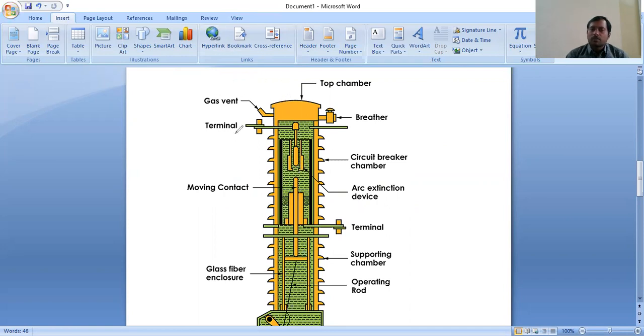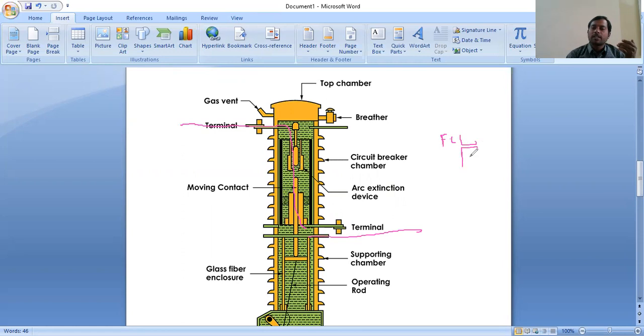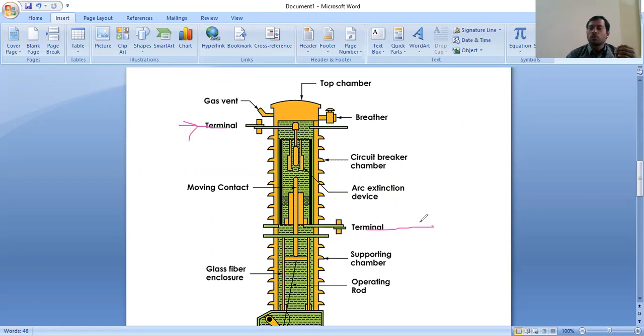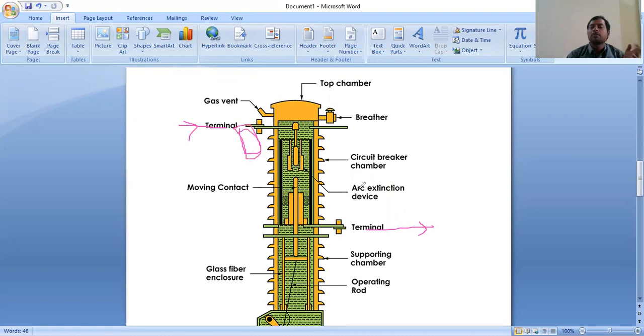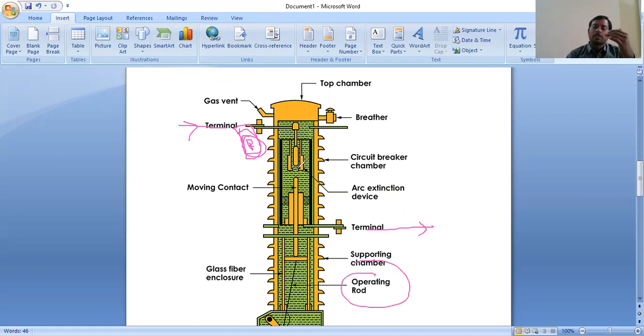In the normal condition, current flows from terminal one through the circuit breaker to terminal two. Both the fixed contact and the moving contact will be in contact mode — this is the normal condition. In the abnormal condition, whenever excess current flows from terminal one to terminal two, the circuit breaker is provided between these two terminals. Whenever high current flows through the circuit breaker, the relay operates. The relay senses the high current and gives the information to the circuit breaker, which then pulls the operating rod. After pulling the moving contact towards the downward, arc will be found between the fixed contact and moving contact.